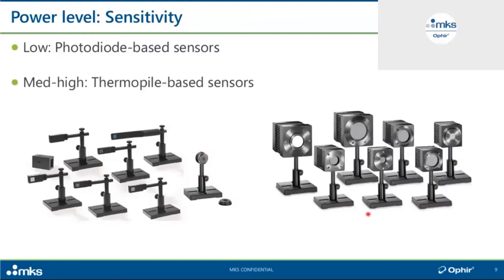Here's a section showing some typical thermal sensors for measuring moderate and upward power levels. You can see there are different size apertures, different kinds of absorbers, some with built-in diffusers, and some with fins on the sensor body designed to serve as a heat sink for power levels high enough to need that.